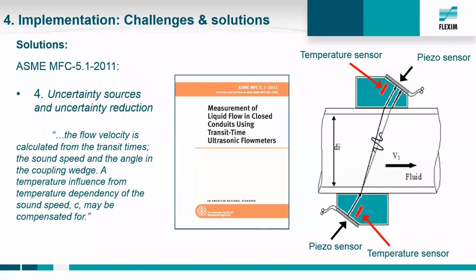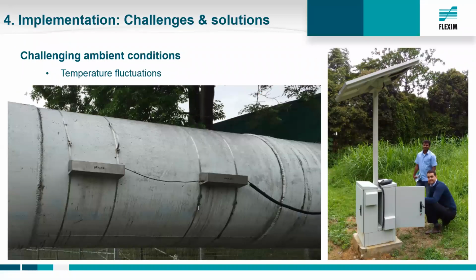So what can happen? We have seen this slide before. Here we can identify what we learned at the beginning, the reflect mode. We have both transducers sitting on one side, so they are usually affected equally by day and night temperature fluctuations. But when we go with a layout with one sound path or three sound paths, then one transducer would sit on the other side of the pipe, and it could even be that at the same time one transducer is sitting in the shadow and the other is exposed to sunlight, and we easily get a 10 to 20 Kelvin temperature difference. Then we have a local temperature difference, and this can only be compensated when you have a wedge temperature probe in each transducer.